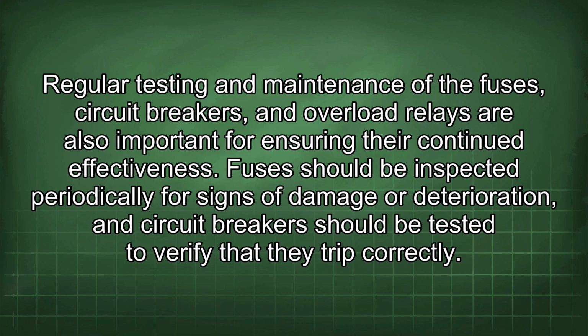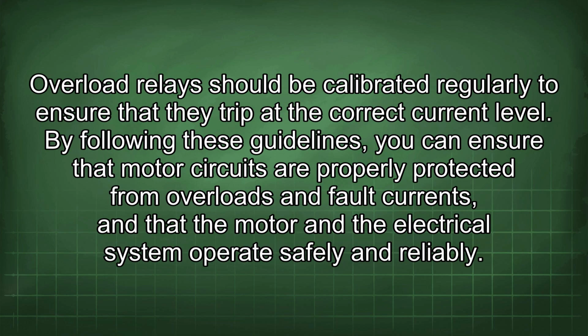Fuses should be inspected periodically for signs of damage or deterioration, and circuit breakers should be tested to verify that they trip correctly. Overload relays should be calibrated regularly to ensure that they trip at the correct current level. By following these guidelines, you can ensure that motor circuits are properly protected from overloads and fault currents, and that the motor and the electrical system operate safely and reliably.